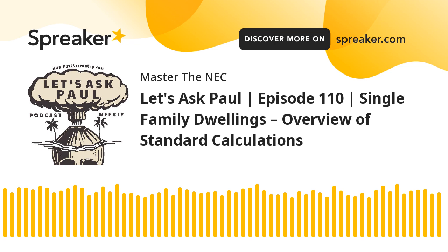So not that we're going to do any calculations here, but if I had a 2-story building and it was 1,000 square foot for each floor, then that'd be 1,000 plus 1,000, that's 2,000. 2,000 times 3 is 6,000 VA. So that is my base value for the general lighting and receptacle loads.